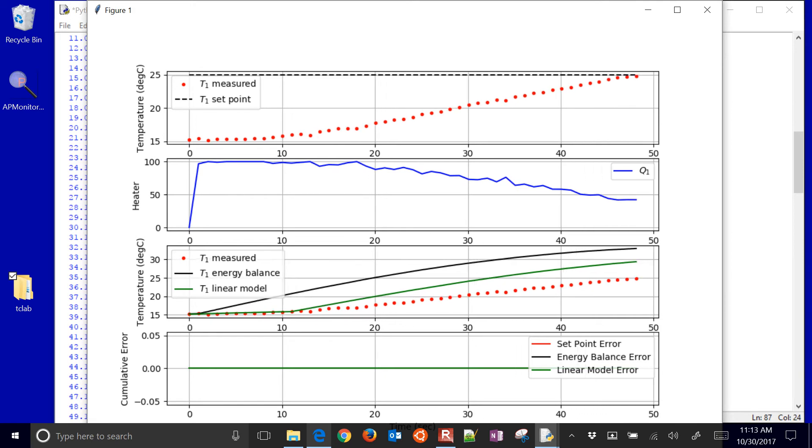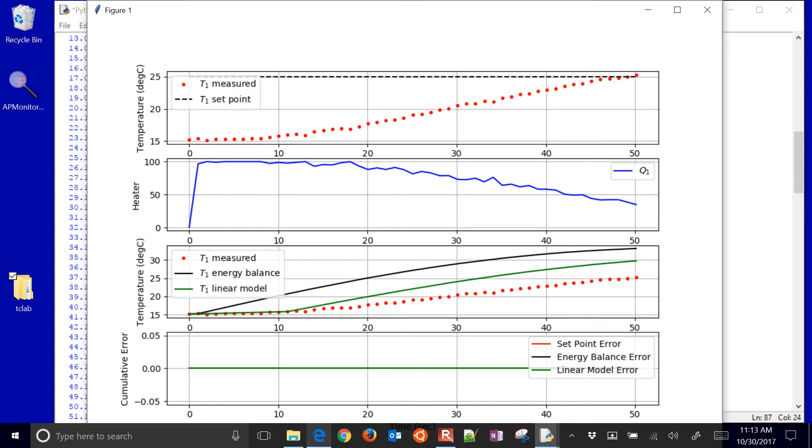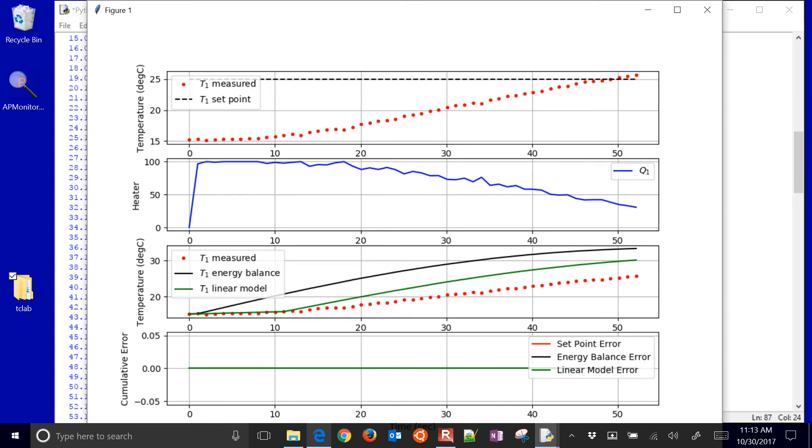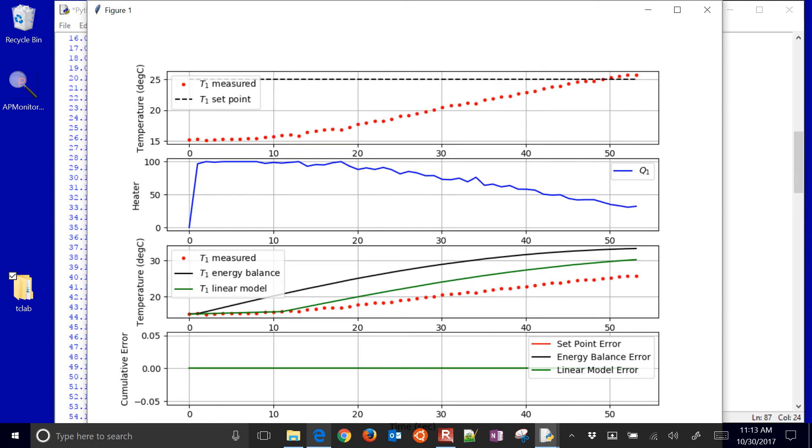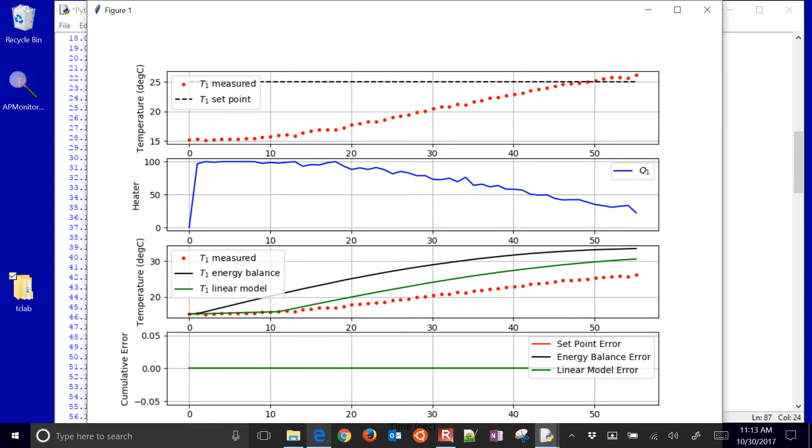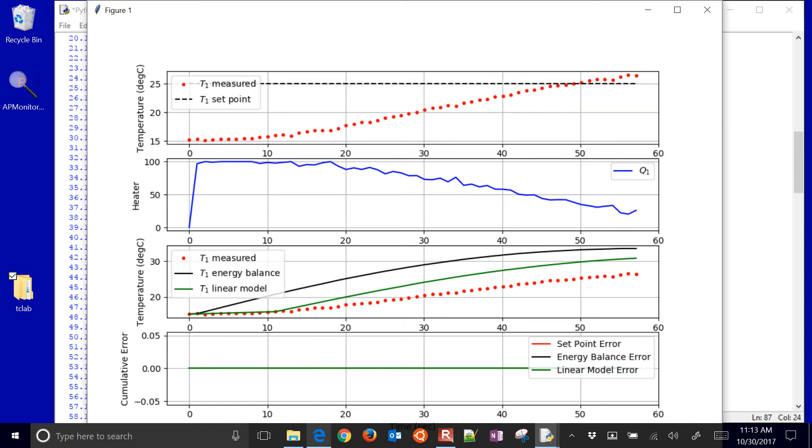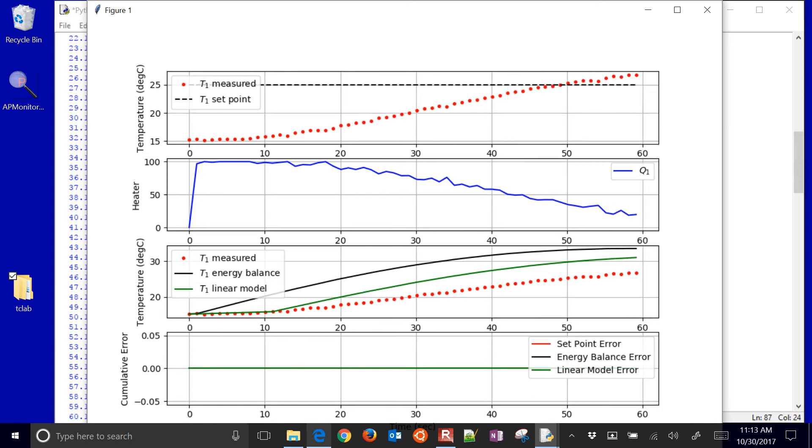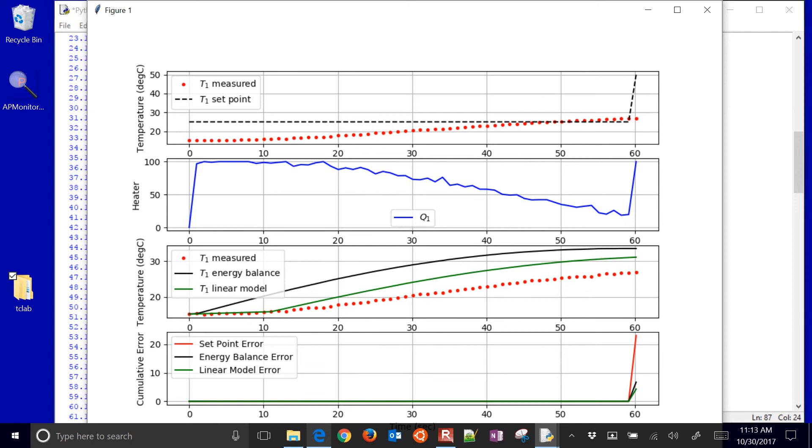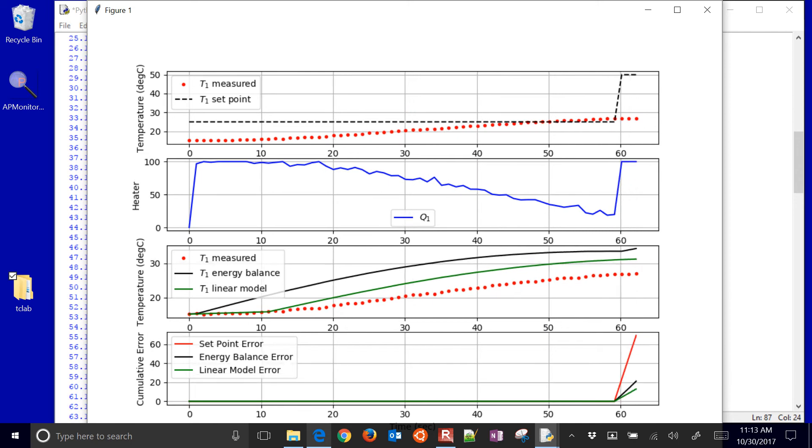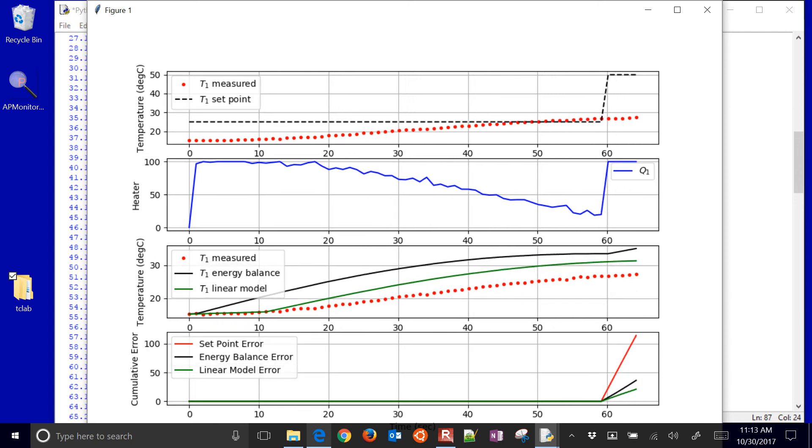At one minute, you'll see that switch happen. You can see the heater is going down. It kind of made its first set point change there. It's going to do just a little bit of overshoot, but basically just hug that set point. And then it's a little bit high right now, but not too bad. So there's the first set point change.